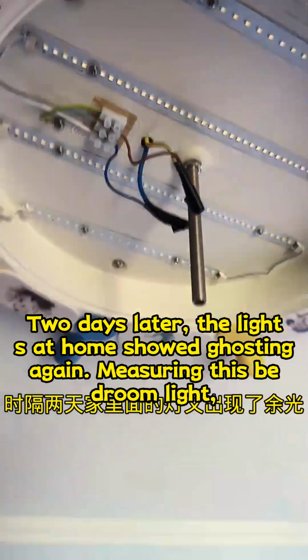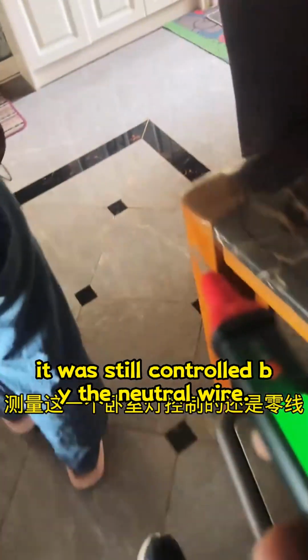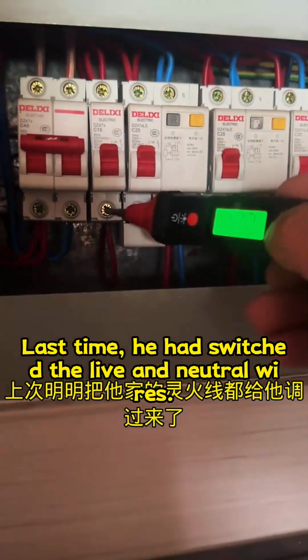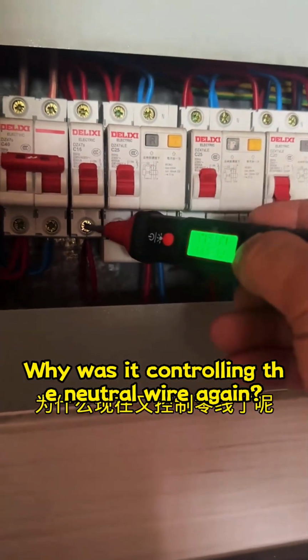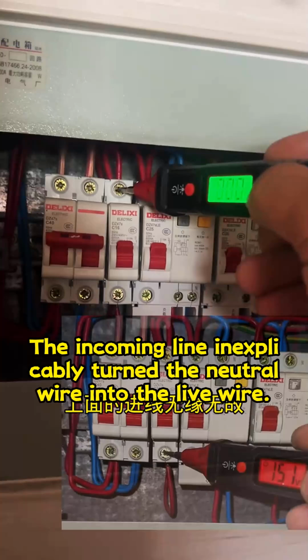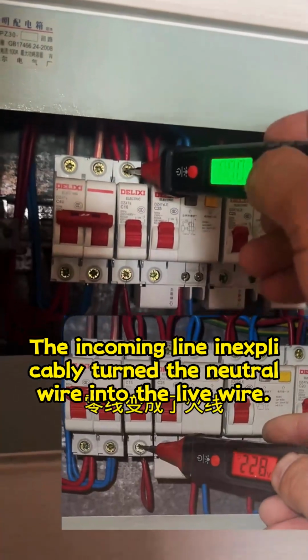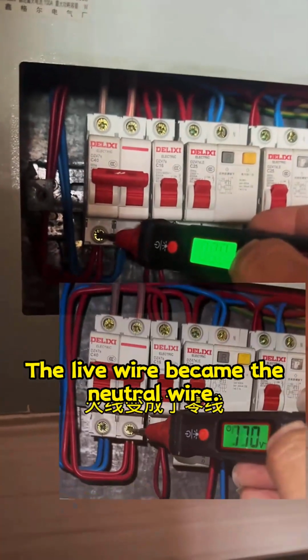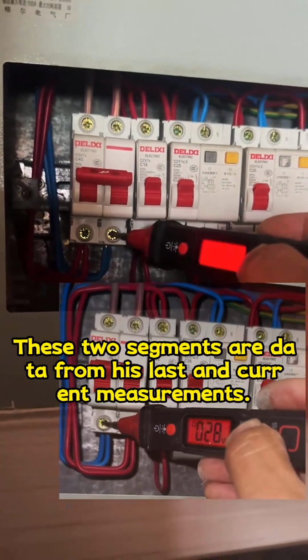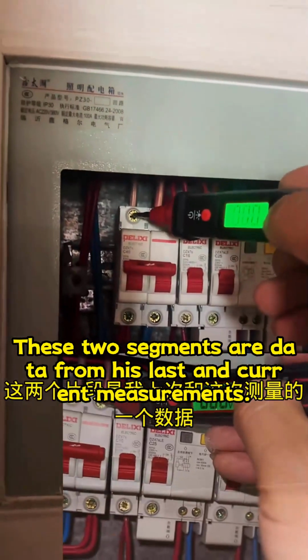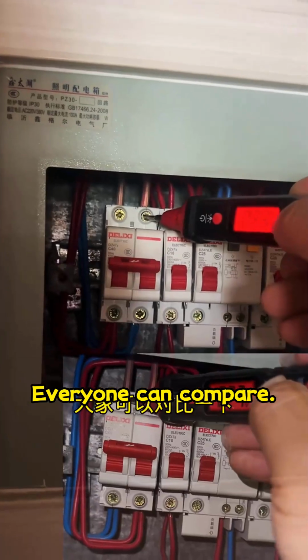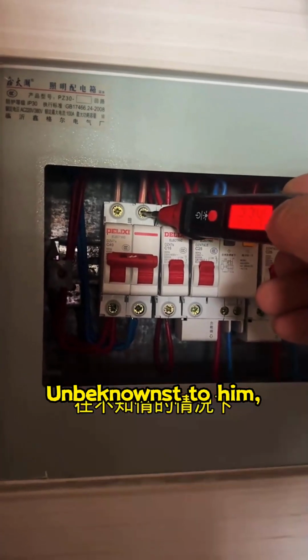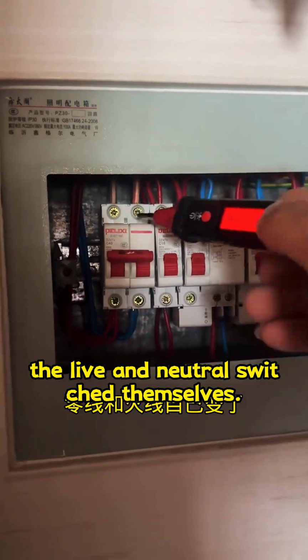2 days later, the lights at home showed ghosting again. Measuring this bedroom light, it was still controlled by the neutral wire. Last time, he had switched the live and neutral wires. Why was it controlling the neutral wire again? The incoming line inexplicably turned the neutral wire into the live wire. The live wire became the neutral wire. These 2 segments are data from his last and current measurements. Everyone can compare. Unbeknownst to him, the live and neutral switched themselves.